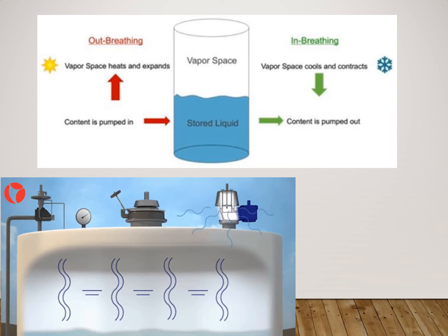This condition is known as out-breathing. In contrast, during the pump-out situation, a decrease of pressure inside the tank occurs. The breather valve is used to purge the tank with inert gas during pump-out. As the pressure inside the tank decreases during pump-out, the breather valve opens and introduces inert gas into the vapor space to maintain safe pressure within the tank. When tank breathing is not needed, the inert gas supply is automatically turned off.